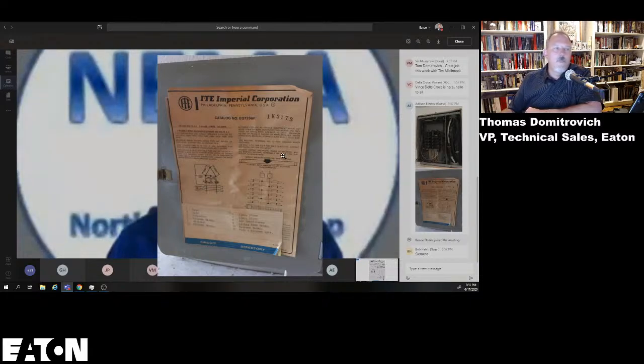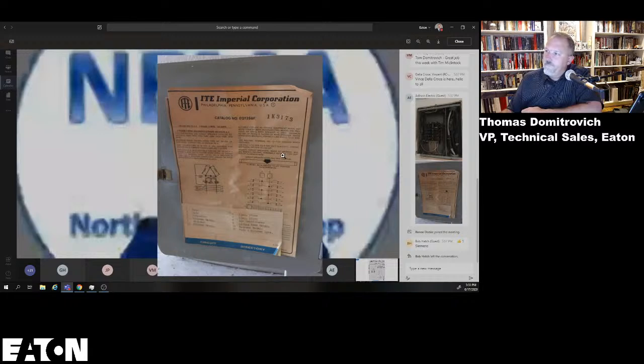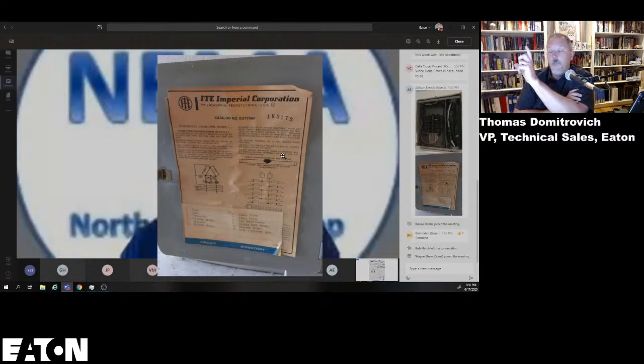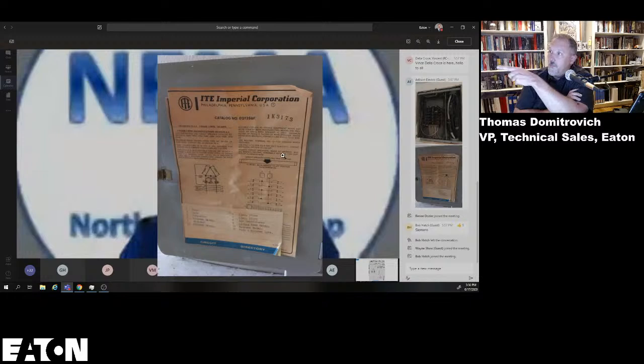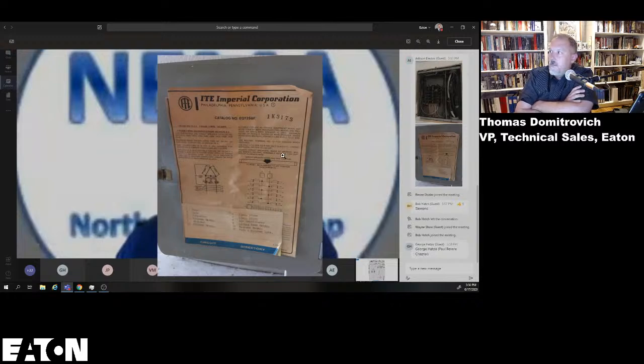What's the question, Jack? Is there a breaker that's classified to go in an ITE panel, an arc fault circuit interrupter breaker? No. That would be classified to go into this old panel. No, sir. You would have to put a little something next to that panel. You could always replace the entire interior. There are products that you can purchase where you could take those guts out, and they're UL listed retrofit interiors, and you can put the brand newest breakers in that. But there's no classified products that will go into an ITE panel board.